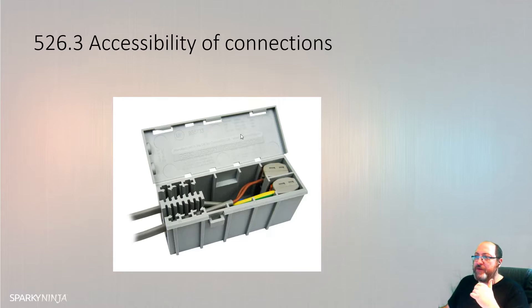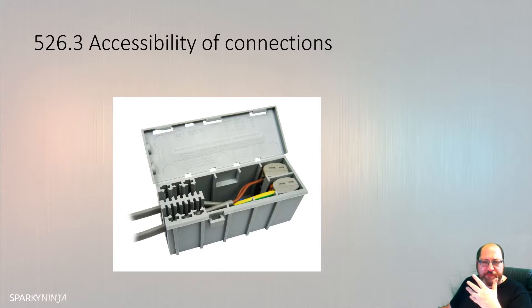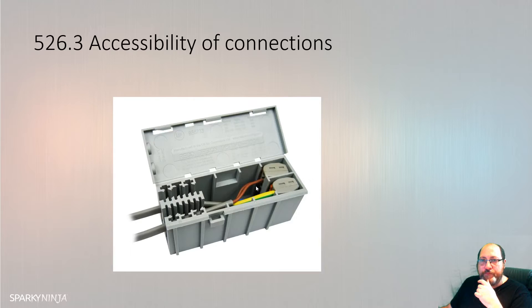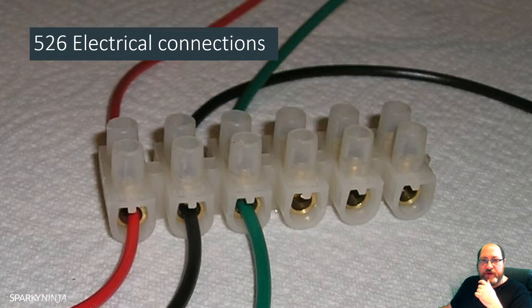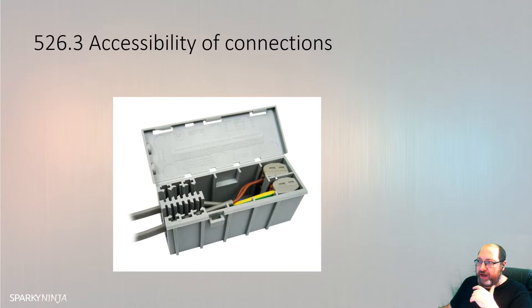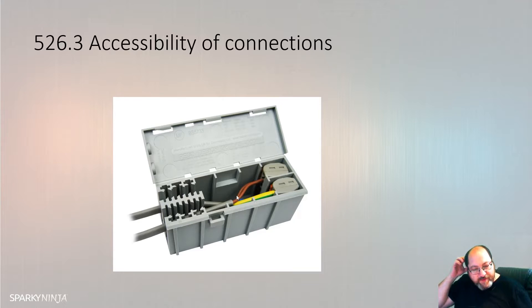Or equipment complying with BS 5733 for maintenance-free accessories, marked with the symbol MF. This came out a few editions ago, and we've seen a big change in attitude — push connections are now a common method. It's okay to be maintenance free as long as it's terminated in a recognized maintenance-free way. The enclosure has to have this MF symbol, so do make sure any maintenance-free connection has been correctly selected for that purpose.